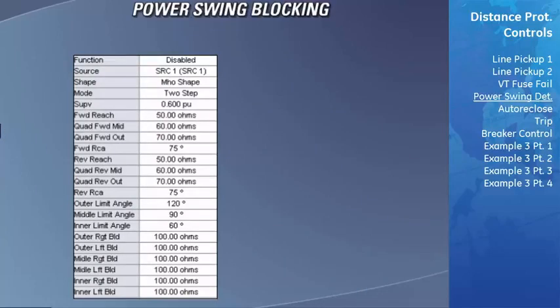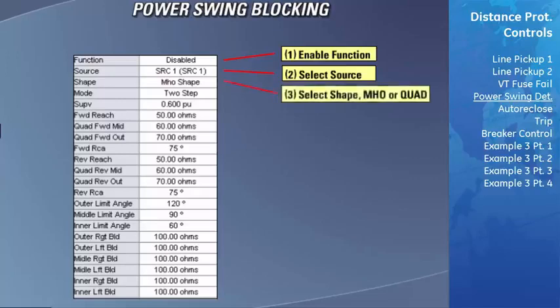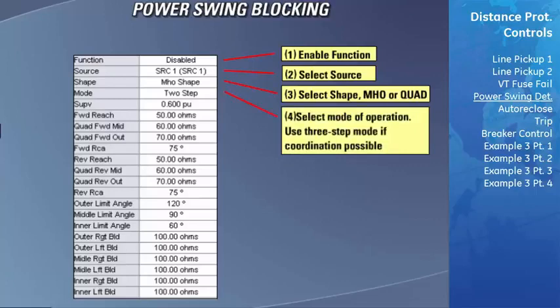The power swing detect function has the following settings that need to be configured for each application. In order to use the power swing detect function, the function field must be set to enabled. The source setting defines which currents and voltages will be used to detect the power swing. This setting needs to be the same as the source used for the distance zones of protection. The shape field allows you to set the power swing blocking zone to be mho-shaped or quadrilateral shaped. The mode setting lets you specify if the power swing blocking feature will be using 2-step or 3-step coordination to detect a power swing. The supervision field specifies the minimum amount of positive sequence current that must be available before the block feature will take effect.